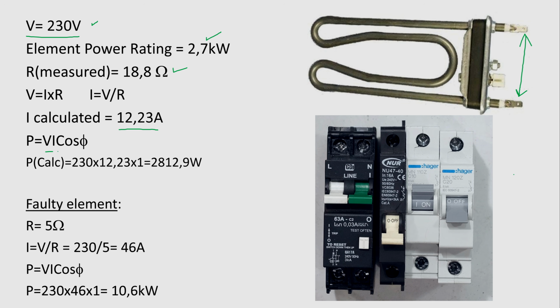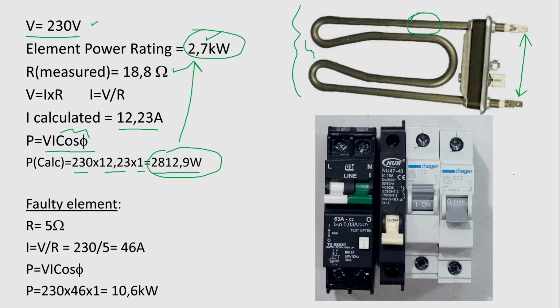Using the power VI cos phi formula, if I work out what the calculated power would be, I get 230 volts. In your case it might be 110 volts or 220 volts, but in my case it's a 230 volt supply times the current times 1, because the power factor is close to 1, because this is basically just a resistor, and I get 2.8 kilowatts. Now if the power factor was say 0.96, yes, it would be closer to the 2.7. It's a slight inductance in there, but it's mostly resistor. But the point is that the calculated power and the stamped power, what says on the body, are very close, and that is how I know that this resistance value of 18.8 ohms is a realistic value.